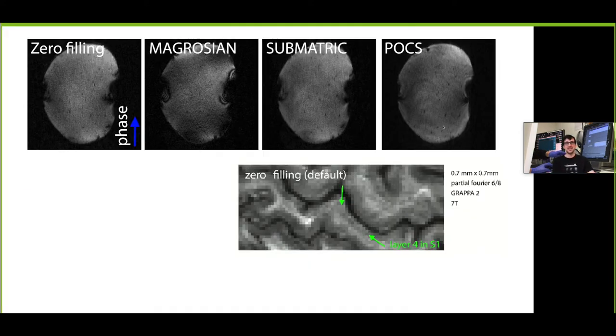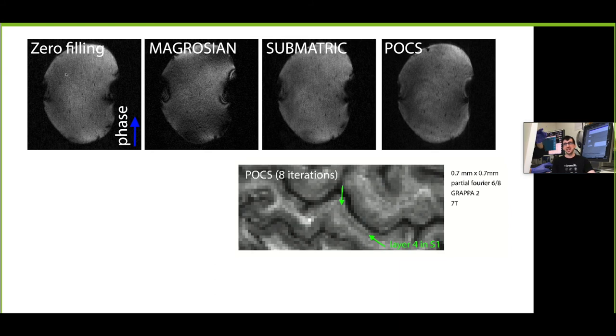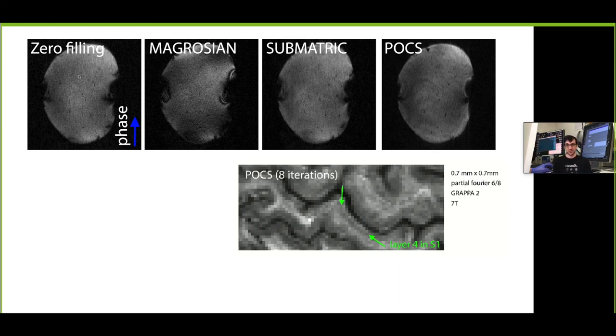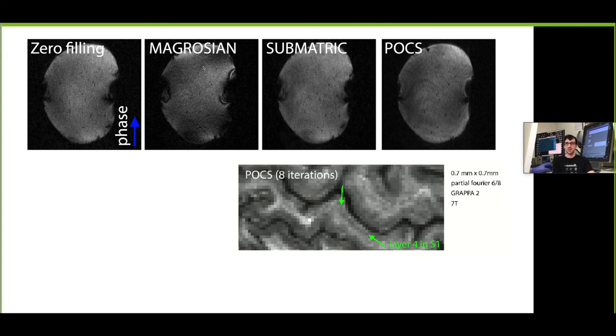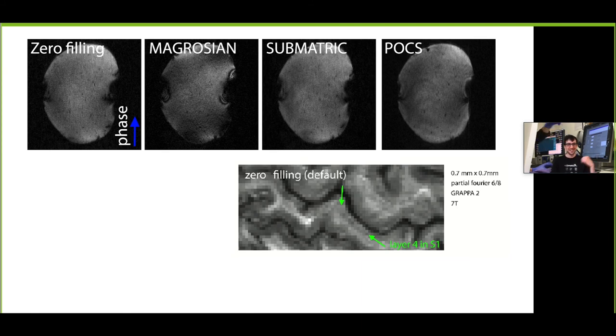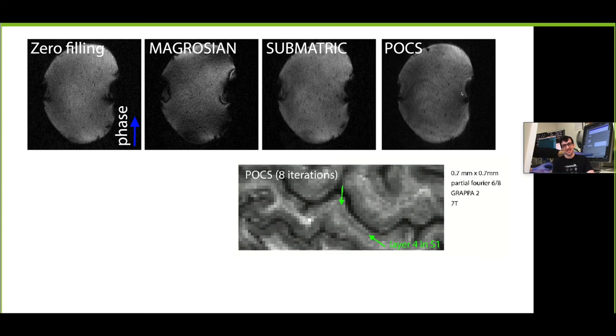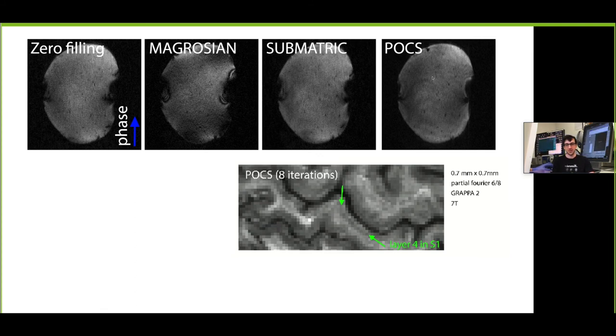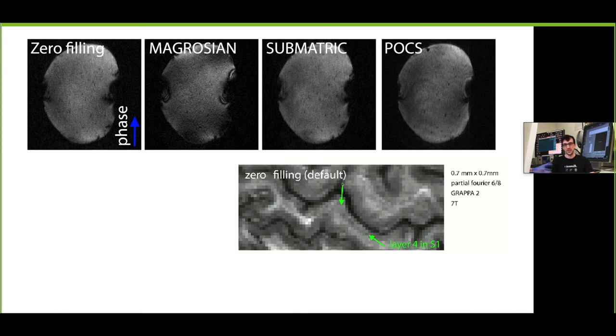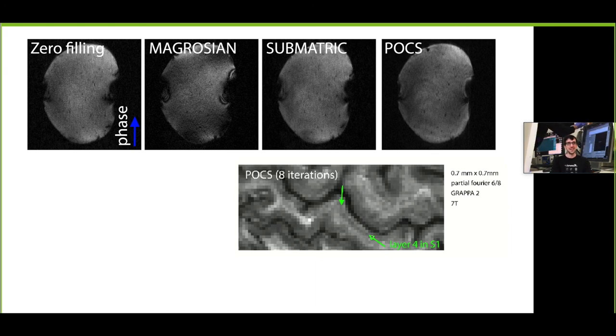There are a few algorithms implemented in Siemens. For example, zero filling, the default for gradient echo BOLD, which is I think the worst way with respect to the blurring but the best way with respect to tSNR. Margosian algorithms really nicely recover most of the local information however it's hugely sensitive to these EPI B0 inhomogeneities like these dark spots which I think we will encounter a lot during the artifact session later. POCS is kind of a compromise between Margosian and zero filling and which is less sensitive, still sensitive though with dark spots all around. Here switching back and forth between zero filling and POCS with eight iterations you can see that you don't recover a lot but you recover a bit, for example here the layer four in the sensory cortex.